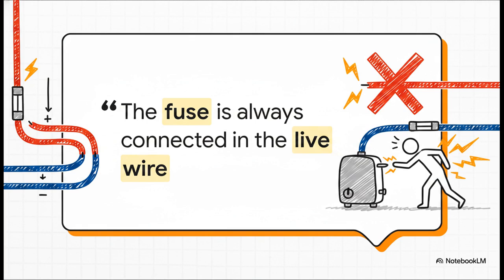If it's accidentally connected to the neutral wire instead, and a surge hits, sure, the fuse will still blow and the appliance will shut down. But that appliance is still directly connected to the high-voltage live wire. So if you go to inspect it, you become the new path to the ground, and you'd receive a fatal shock even though the device is technically off.